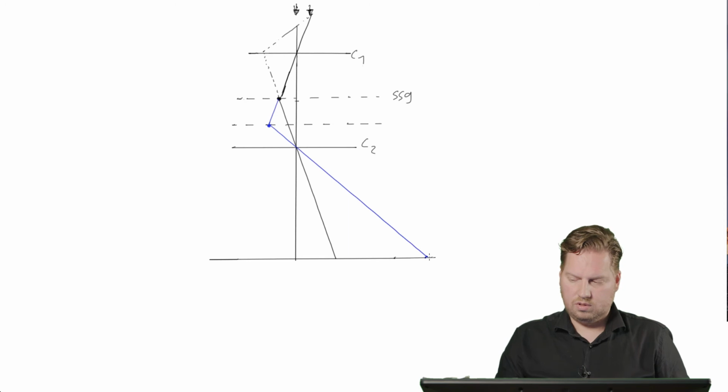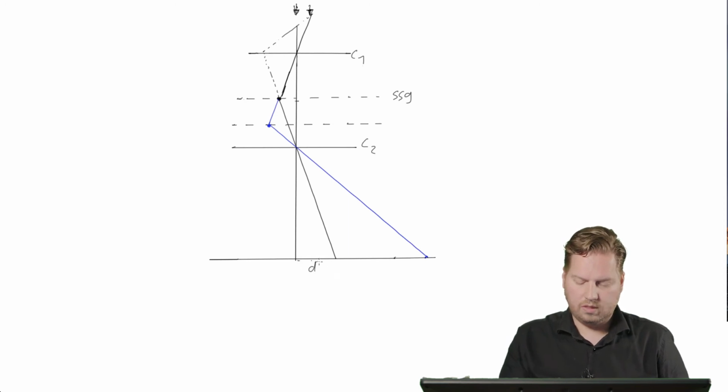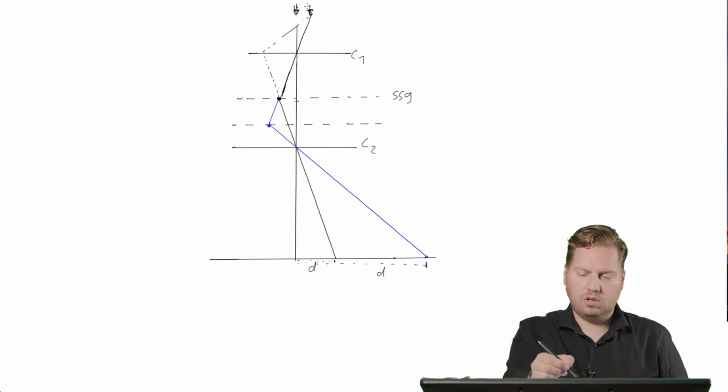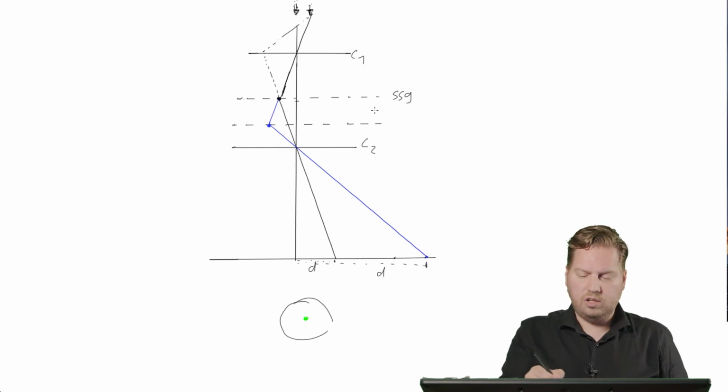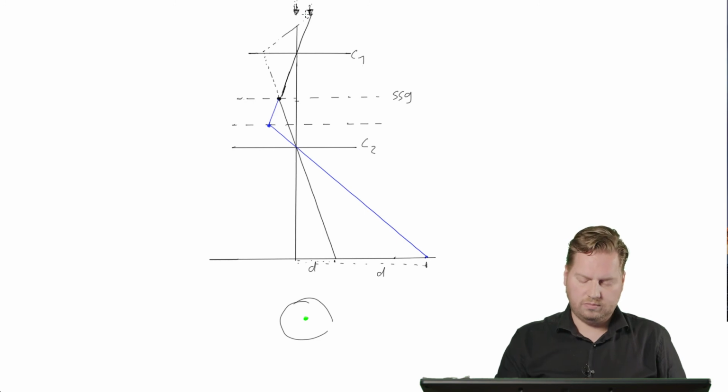What now effectively happens is this distance here is magnified. So if you change the spot size, what you'll see is that actually your spot will move. If your gun is shifted and you have your light on the screen, so this is our fluorescent screen, and we have a nice spot of the electron beam, maybe we want to make that green, because it's a fluorescent screen. You have your spot here. If we would change the spot size and our beam would be shifted, then that spot would move. If we go from spot size 9, where it would be closer to the optical axis, to spot size 3.